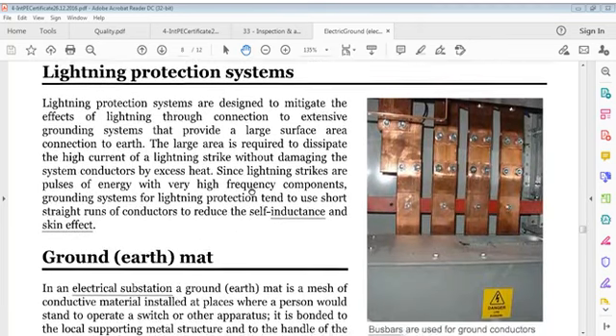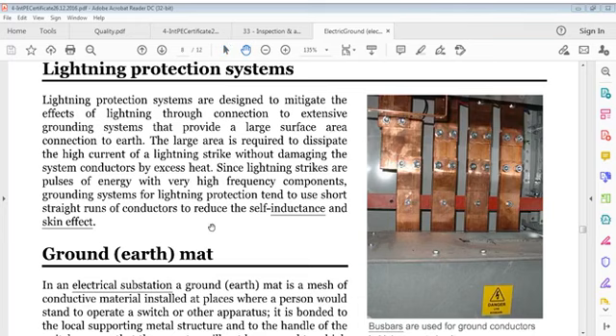Lightning protection system. Lightning protection systems are designed to mitigate the effects of lightning through connection to an extensive ground system that provides a large surface area connection to earth. Large areas are required to dissipate the high current of a lightning strike without damaging system conductors by excess heat. Since lightning strikes are pulses of energy with very high frequency components, grounding systems for lightning protection tend to use short straight runs of conductors to reduce self-inductance and skin effect.